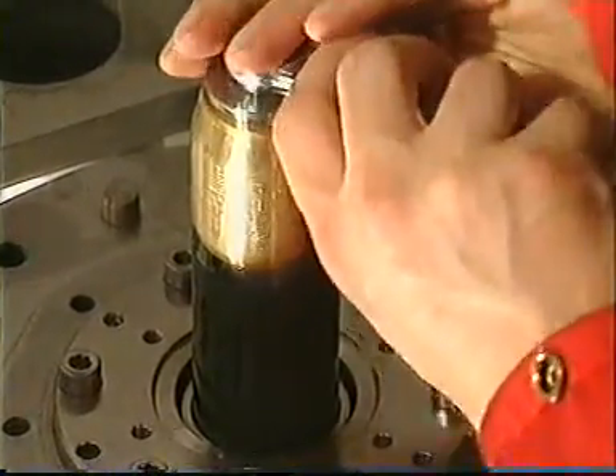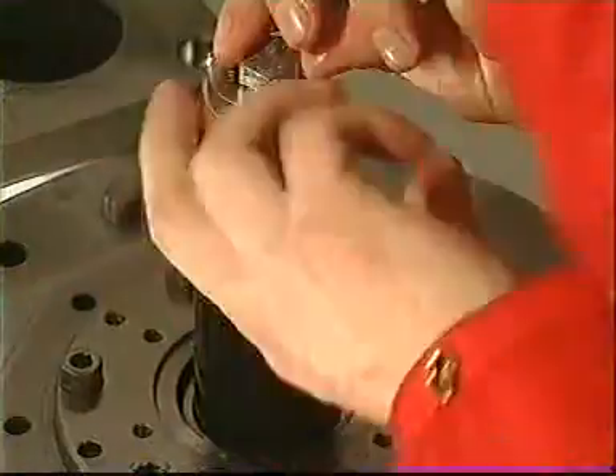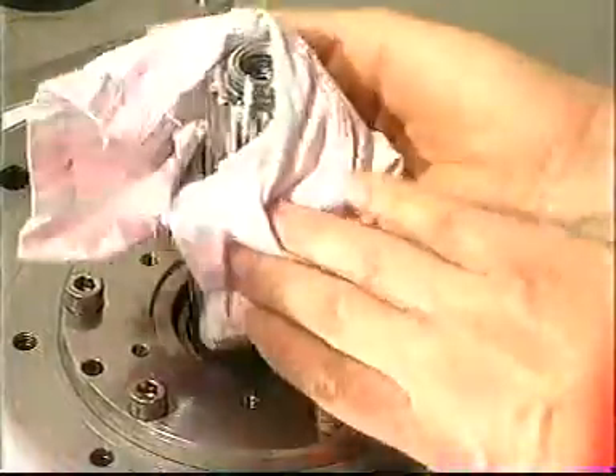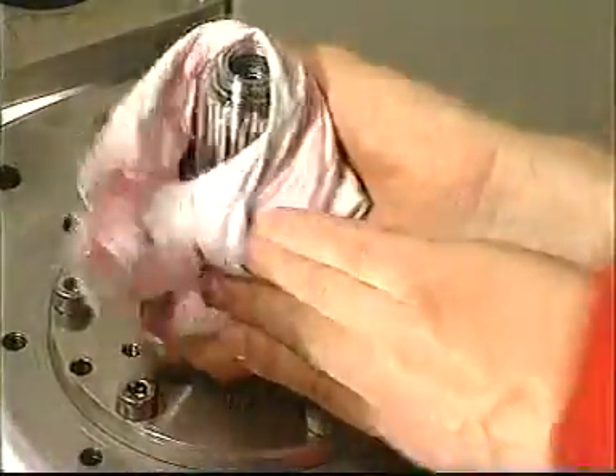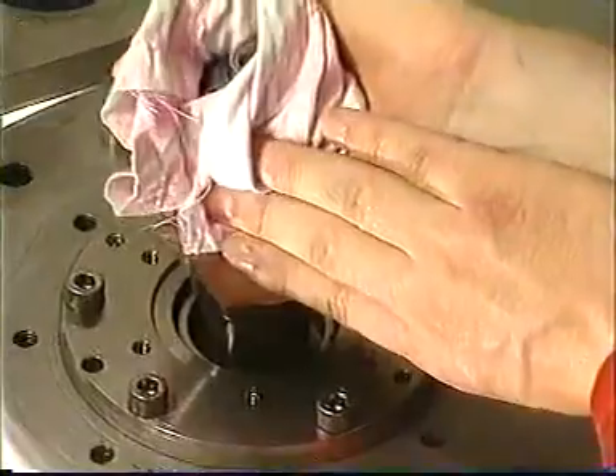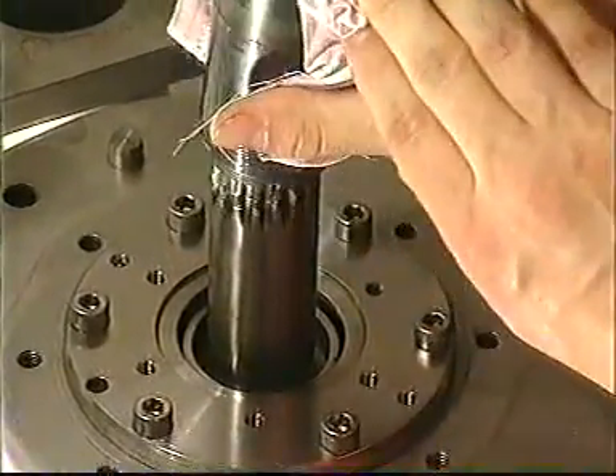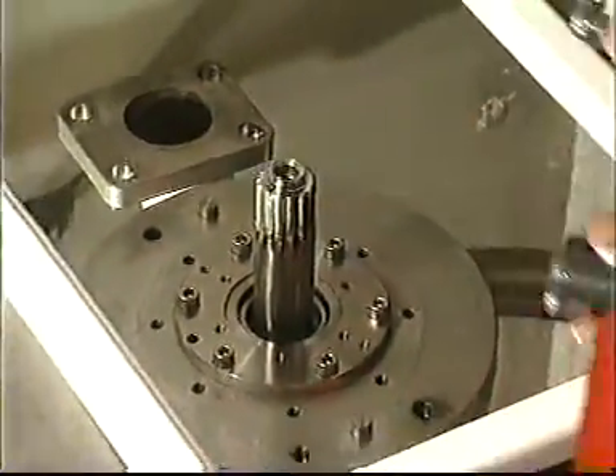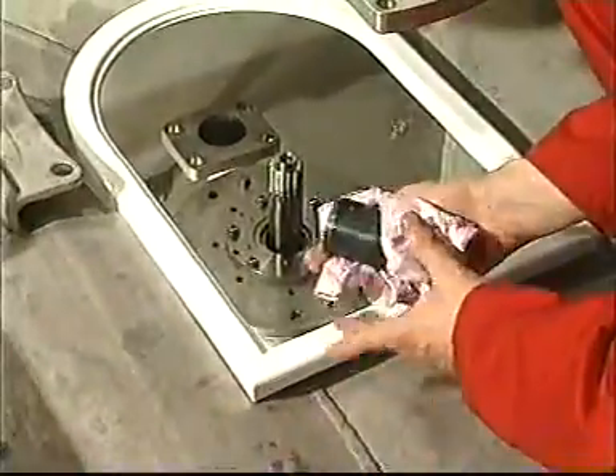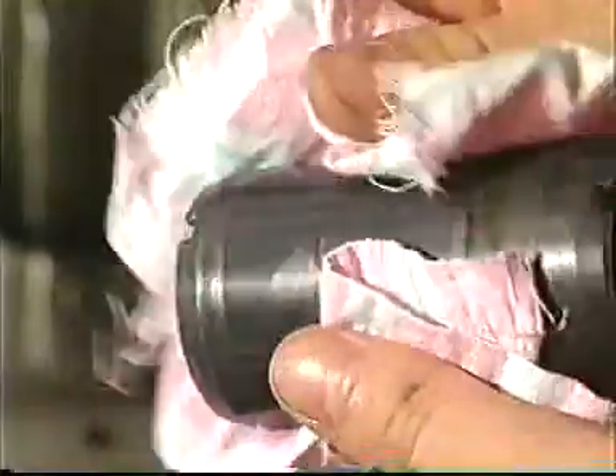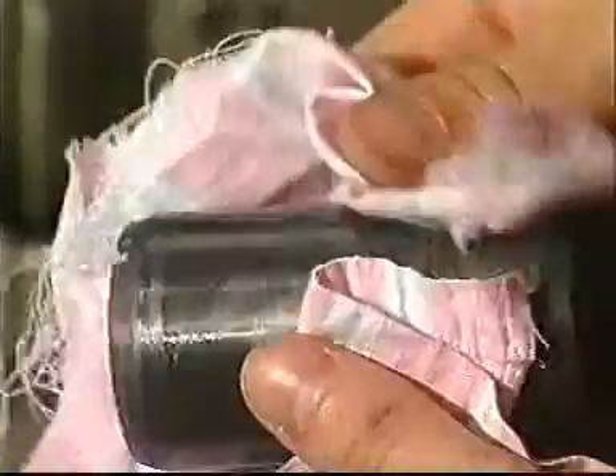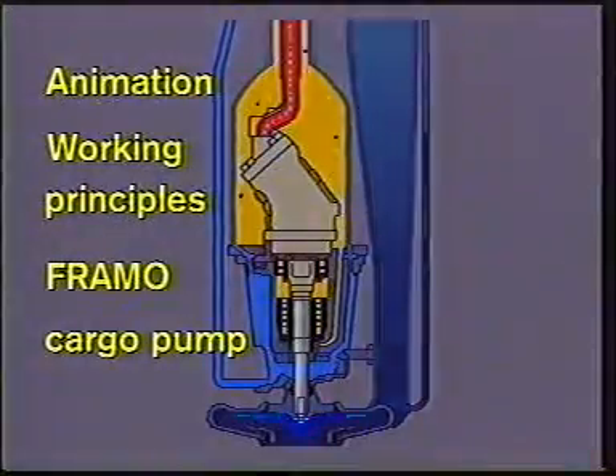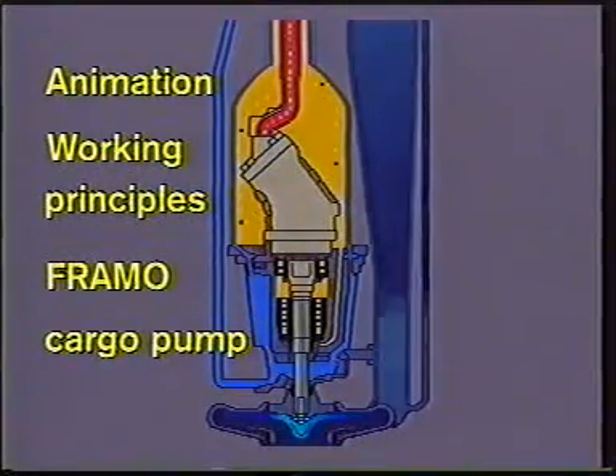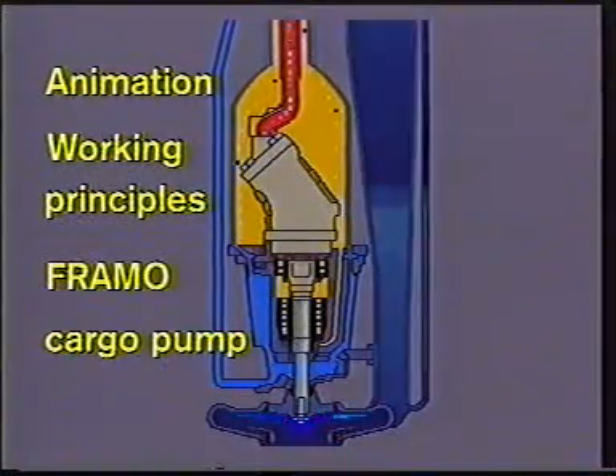Take away the assembling cylinder and pull out the ceramic sleeve and check the parts carefully. The ceramic sleeve must be handled very carefully as it is brittle and may crack if dropped or mishandled. If necessary, it is also possible to change all rotating parts in the cargo pump when the pump unit is still hanging on the pipe stack.